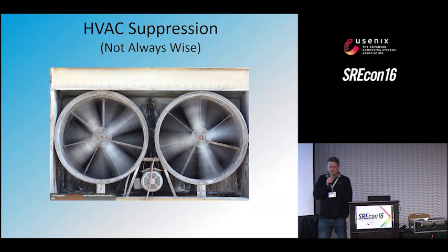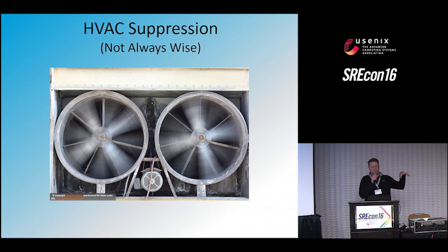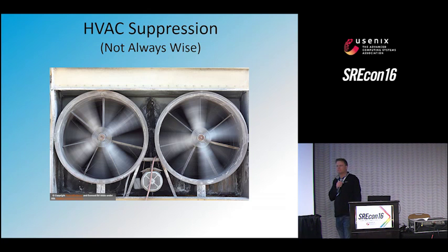HVAC suppression. This was another instance where we actually had one HVAC failure on the roof. It just got a little warm in one part of the data center and triggered a soft fire suppression system. What's the first thing that happens? Shut off all of the HVAC. All of it. Data centers get hot really quickly when you shut off the HVAC. We had people running in there powering off systems in 5-minute shifts with wet cloths over their face. Ugly.